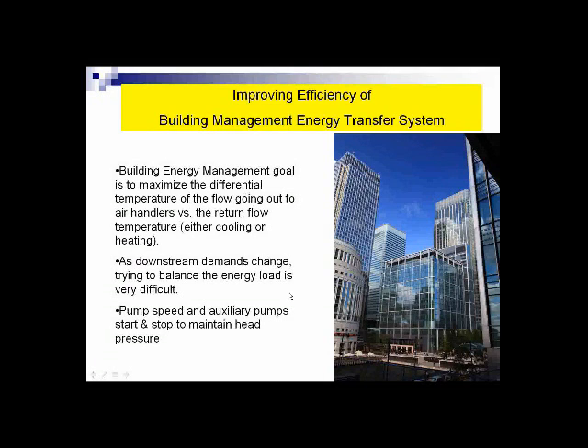The problem is that as the downstream demands change, trying to balance the energy load is very difficult. And what I mean by the demand changes is, if you were in, let's say, a university campus, and suddenly one of the big meeting halls was opened up and it had been closed overnight, and suddenly they need to cool this room down from 85 degrees down to 72, and that's going to put a big load on the chillers. Consequently, the pump speed will change. Auxiliary pumps may kick in, and they will do everything they can to create the head pressure that's required to try to meet the demand of that.